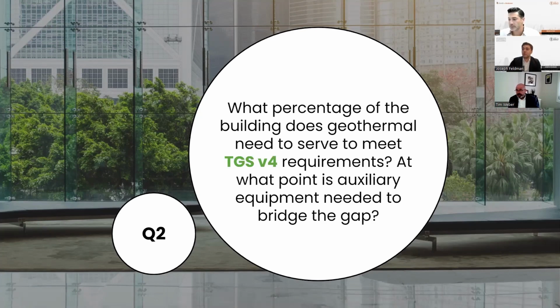Geothermal may address 40% of the peak load, and I think in our industry we often over-index on the peak. So 40% of the peak, but Bram also mentioned that's equivalent to about 80% of the aggregate. The aggregate is really the key number - that's the overall heating and cooling, which is really about the overall carbon reduction. So maybe we only get 40% of the holes we'd like to see for 100% of the peak, but that 40% of the holes provides 80% of the aggregate, which is 80% of the carbon reduction, 80% of the energy reduction. Those are the metrics these policies look at - they're less concerned about the peak, more concerned about the aggregate. So we're still within striking distance of 100% geothermal building, just with a fraction of holes and a boiler/cooling tower to provide the remainder. Would that be a fair assessment, Bram?